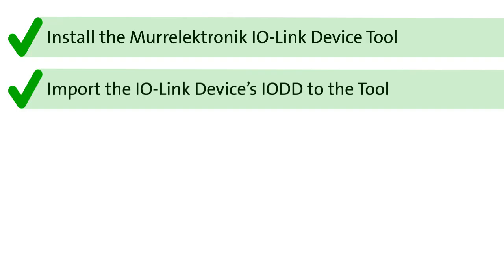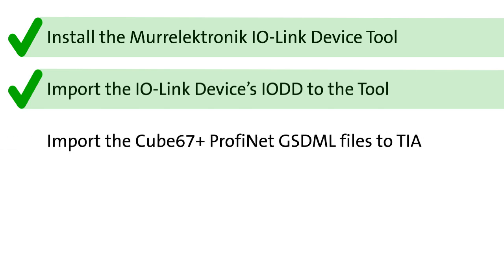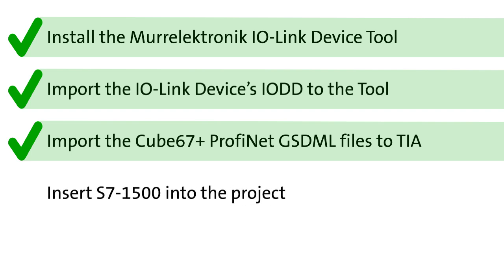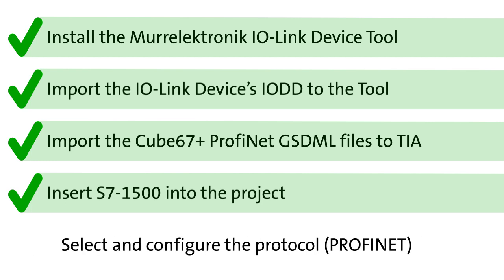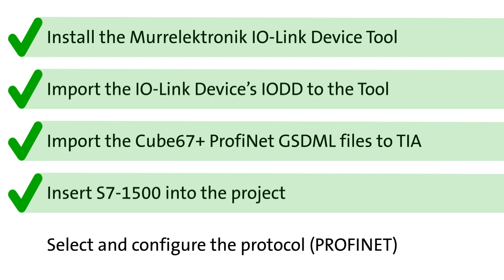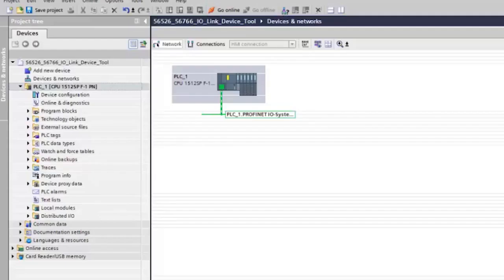Here are the things you should have done by now: Install the Murrelektronik IO-Link device tool. Import the IO-Link device's IODD to the tool. Import the necessary PROFINET GSDML files for the Cube67 bus node that you downloaded from the device's page in our online shop into the TIA portal and configure the PLC S7-1500. Select and configure the protocol which is PROFINET. Now your screen should look like this.